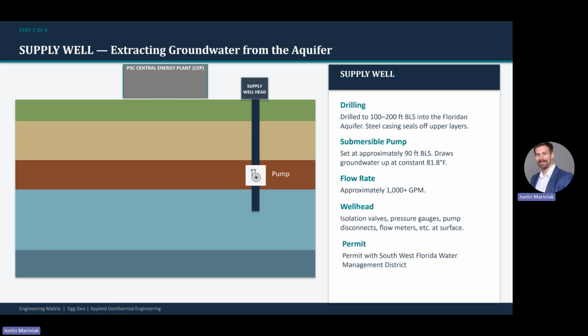To begin construction, we need to drill a supply well. This well extends from the surface down through the layers and penetrates the aquifer at about 100 to 200 feet deep. It is composed of steel casing and is grouted to prevent intrusion from above. The wells can produce more than 1,000 gallons of water per minute. The wellheads contain various fittings and gauges for monitoring the system. It also includes electrical disconnects for the submersible pump down in the well that pumps the water out. These wells are permitted by Southwest Florida Water Management District.